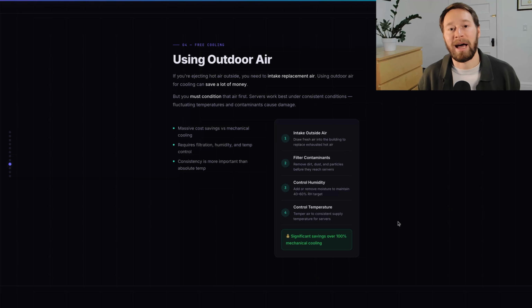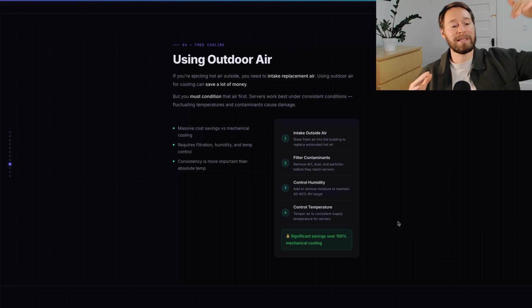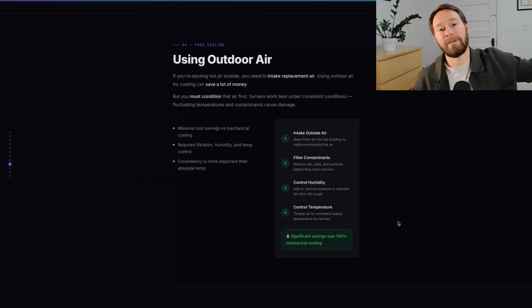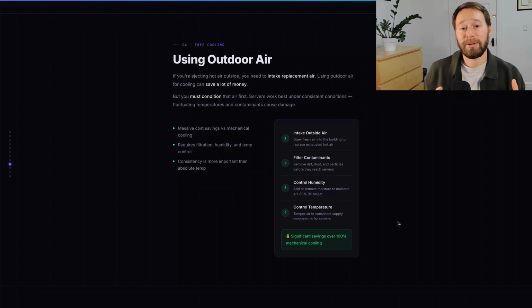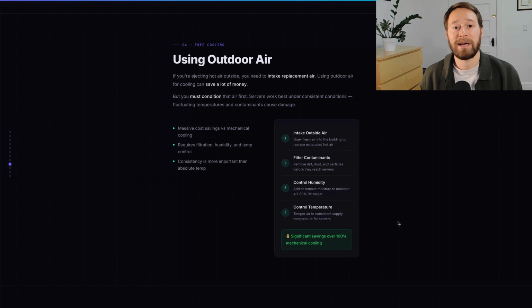There is a design I'll try to find a photo of, from a proper cloud company doing this. They built specialized structures, quasi data centers, with a slanted roof that let all the hot air rise to the ceiling, maybe 30 or 40 feet up. Because the roof is slanted, there's an opening along the top that directs all the hot air out of the building. All their air intakes were down at the bottom, letting the floor basically be outside temperature. So you've got conditioned air coming in from outside, and hot stale air going out the top. If you're doing this in your own building, you have a lot of engineering freedom over how to direct that air for free cooling.